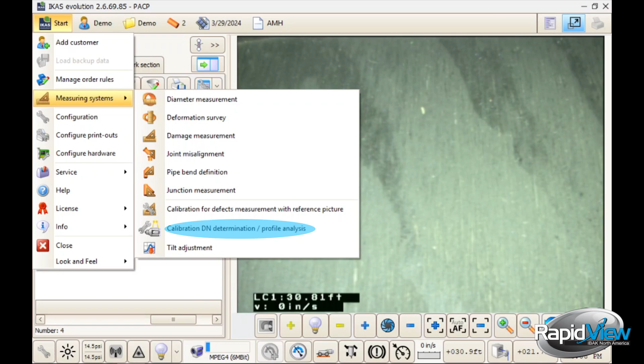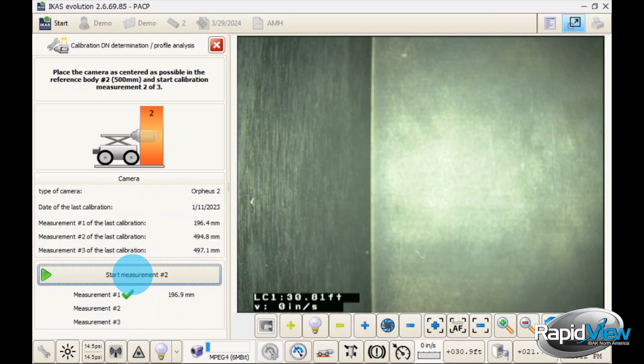The directions at the top will walk you through this, but just for reference, you will do the 200 millimeter box, which is the smaller box, first, and then you will do two separate measurements in the 500 millimeter box. Once you get to this screen, you need to insert your box in there. Once it's inserted, we're going to hit start measurement. The lights will turn off, your camera will adjust, our barcode will show up, and then after just a second, it's going to say start measurement. We hit that and begin, and your camera head begins to rotate. Once it's done, it'll give us a pop-up giving us our measurement, and we're good to go to move on to the second box.